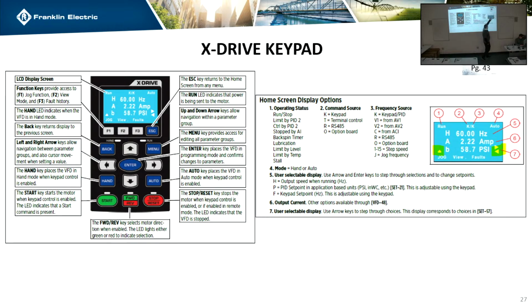Over here, it says K/K. The demo unit should say T/V1. So what that's telling you is, T would be terminal control, which is the inputs. V1 is AV1, so these are wired to look at the speed pot on the AV input. So that's why it's set up like that. KK would just be keypad. And then one that you will commonly see is C, because that's your ACI input. And then anyone that's running a PID, it will say K, because the PID gets its pressure setting from the keypad.